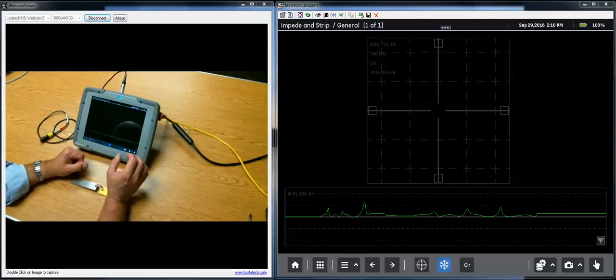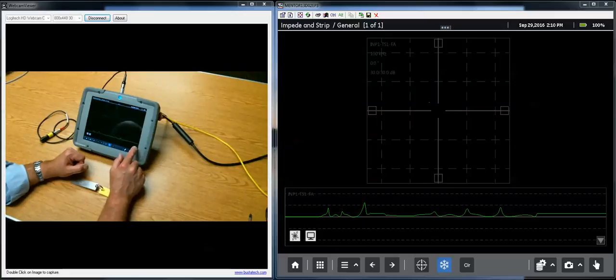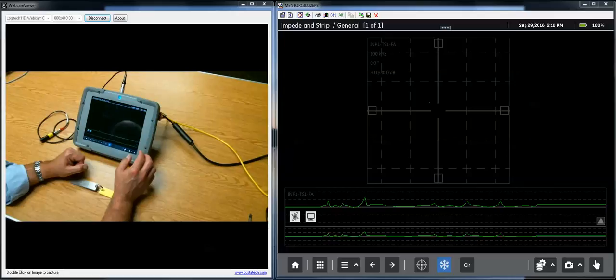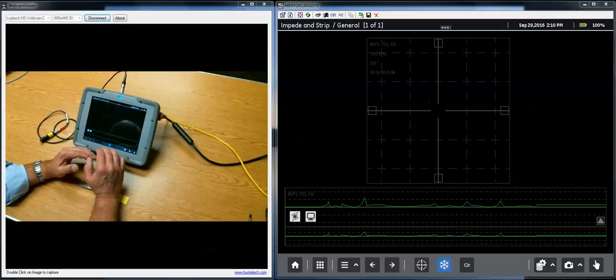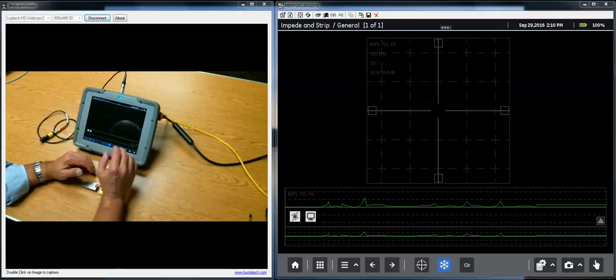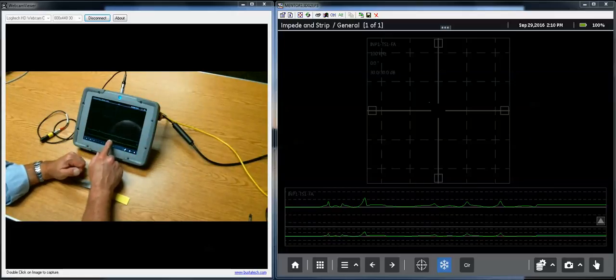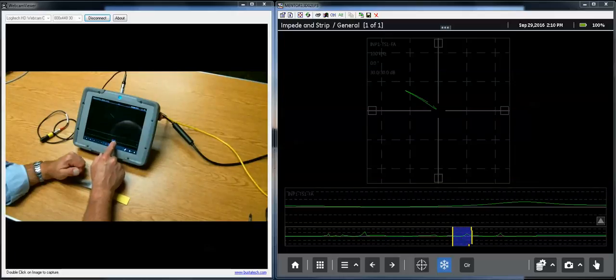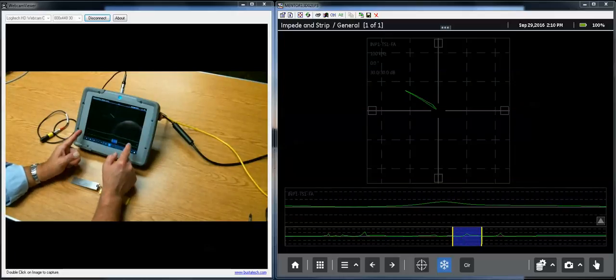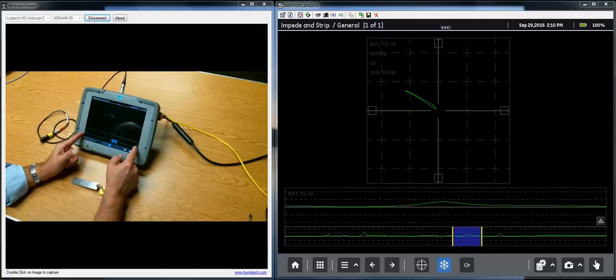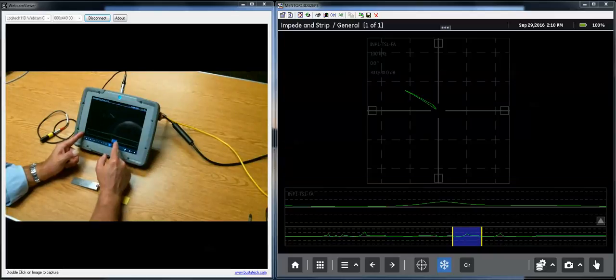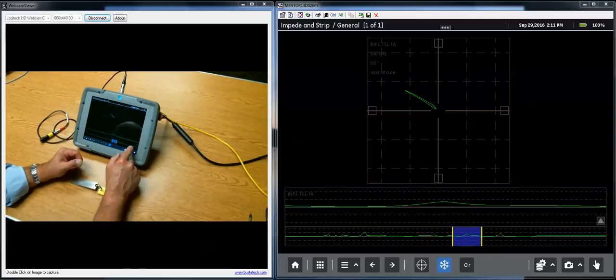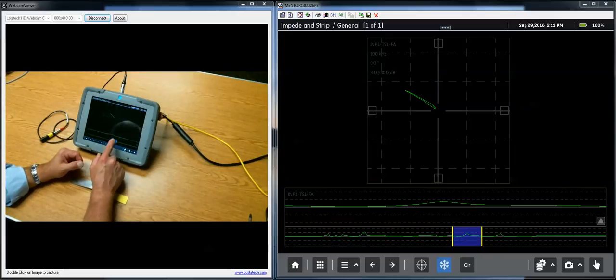So one of the things we can do, if you'll notice down in the lower right corner of the strip chart there's a little button with an arrow. If I press that arrow, the strip chart kind of breaks into two. The lower part of the strip chart is what we call the overview, and that will always show us everything that was in the data buffer that we recorded. So we recorded 10 seconds of inspection and we're always going to see the full 10 seconds down the bottom.